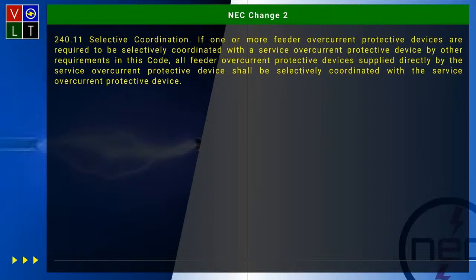We had a job, I kid you not. Ground fault happened in the system and it went all the way out and blew up the transformer, and we had to redo that whole service. It wasn't coordinated, was it? That's where I learned about it, because I was like, why did this happen? It's because that overcurrent device should have opened. Dude, they said blue flames, purple flames came out of the transformer, and then it blew in half. I believe that. How does that happen? They just had basically the whole entire building like main lugged. It was stupid.